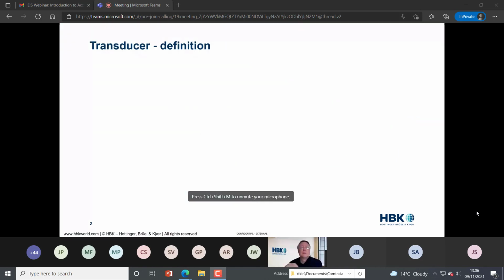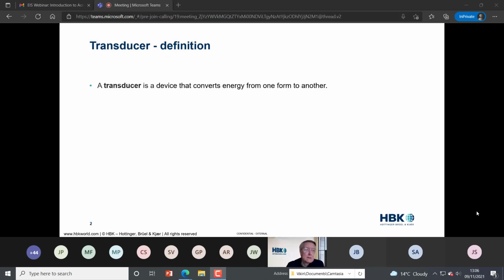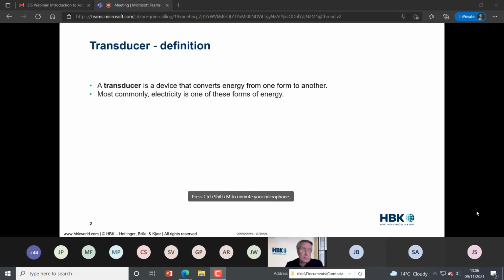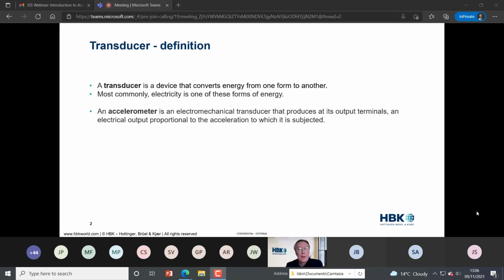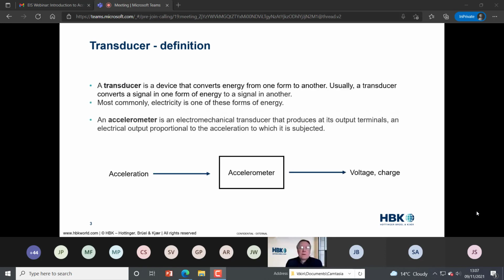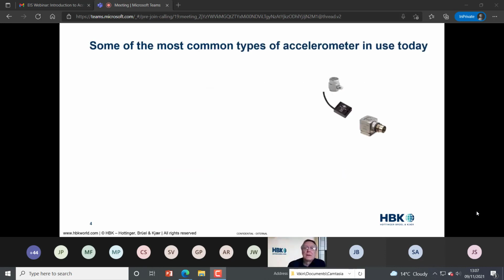Now, an accelerometer is just one type of transducer. But what is a transducer? A transducer is a device that converts one form of energy into another. Very simple. Usually, though not always, one form of the energy is electricity, either to electricity or from electricity. An accelerometer is an electromechanical transducer that produces an electrical output which is proportional to the acceleration that it's being subjected to. So vibration in the form of acceleration is moving the accelerometer, and that produces a voltage or charge analog of that vibration signal. So that's what an accelerometer is.